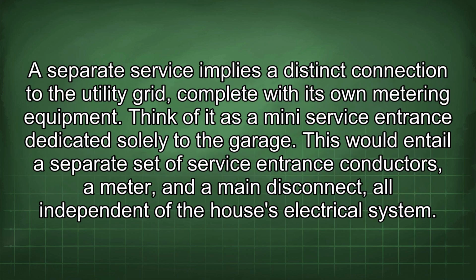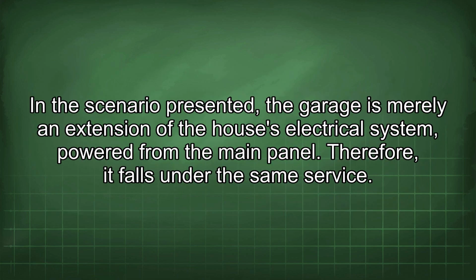A separate service implies a distinct connection to the utility grid, complete with its own metering equipment. Think of it as a mini-service entrance dedicated solely to the garage. This would entail a separate set of service entrance conductors, a meter, and a main disconnect, all independent of the house's electrical system. In the scenario presented, the garage is merely an extension of the house's electrical system powered from the main panel. Therefore, it falls under the same service.